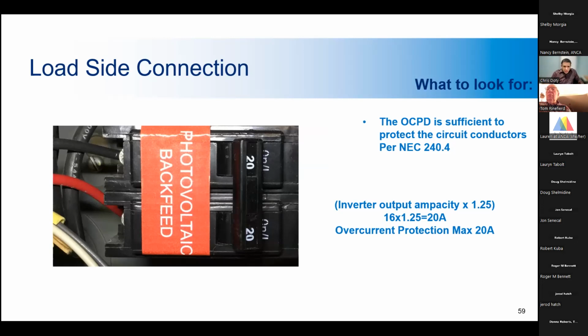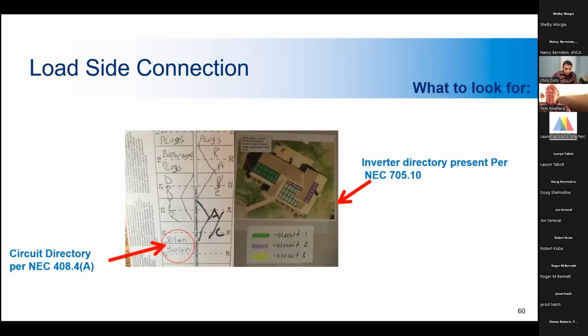And here you can see the standard calculations, just like in the previous one. To determine the sizing of the circuit breakers and fuses, you take 125% of the output current, and it's sized to protect the wiring and the equipment in the system. Most backfeed breakers like this one will be a double breaker. So they're 240 volt, which corresponds to what's in most homes. And you'll have equal distribution on each leg.